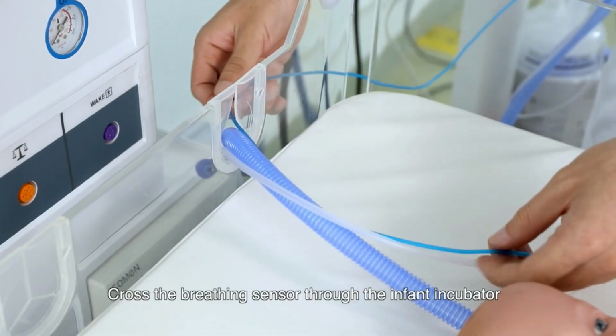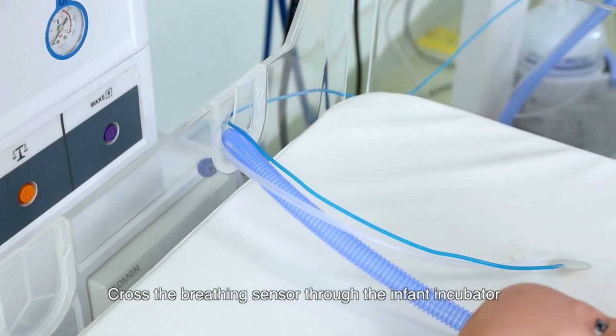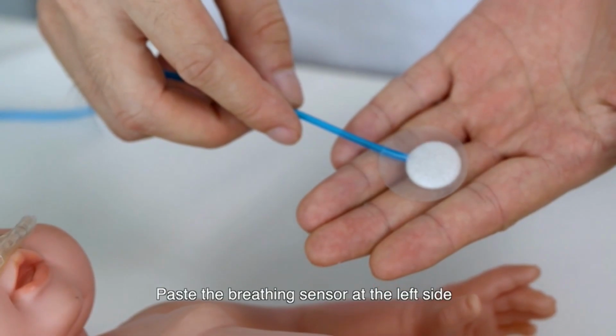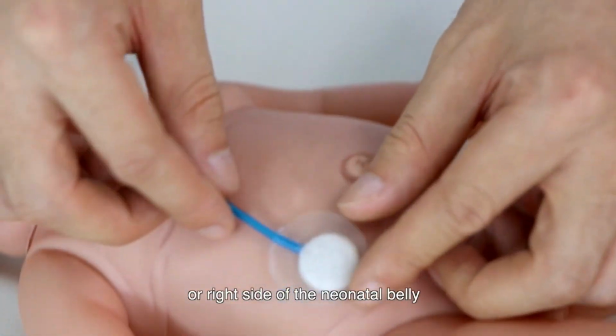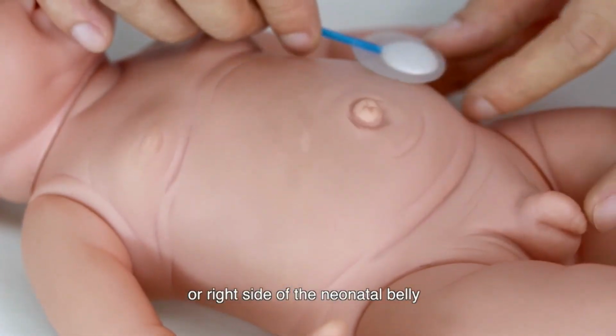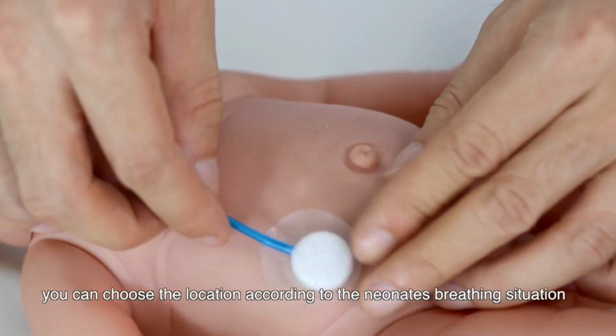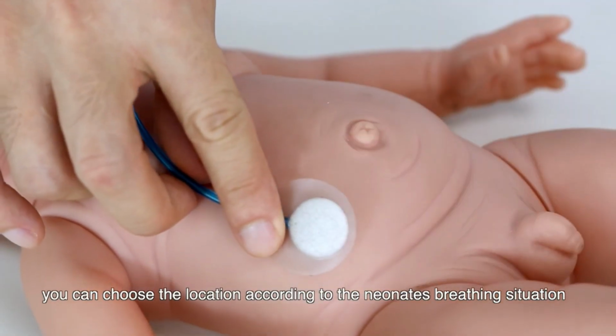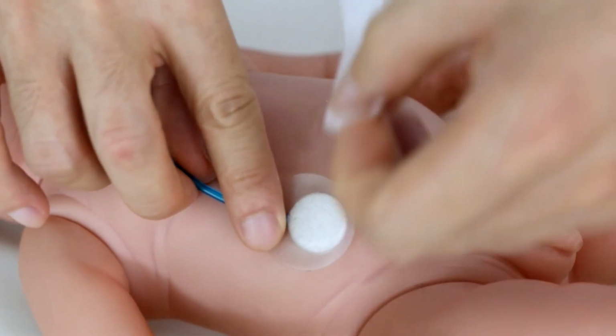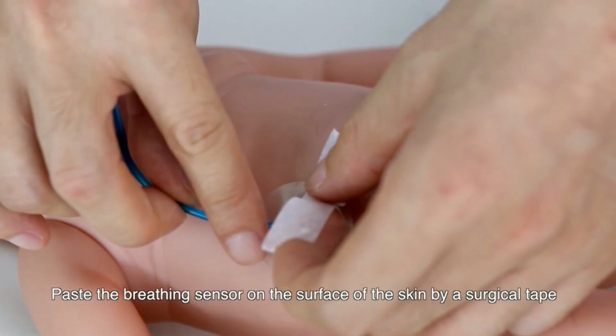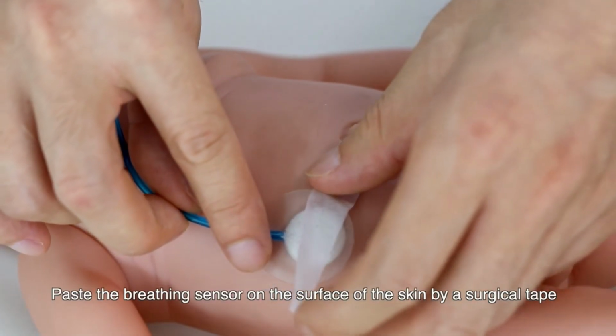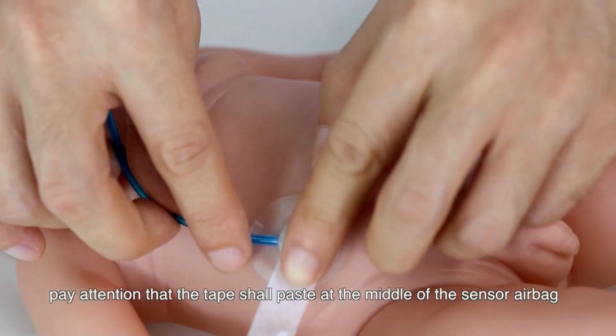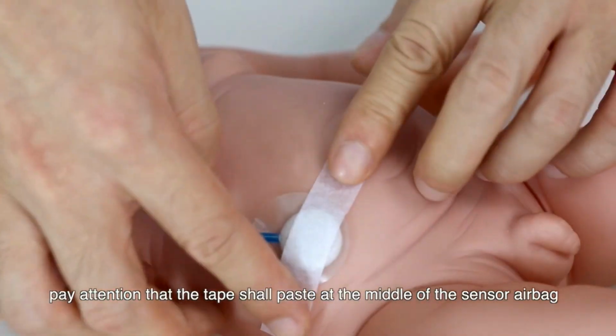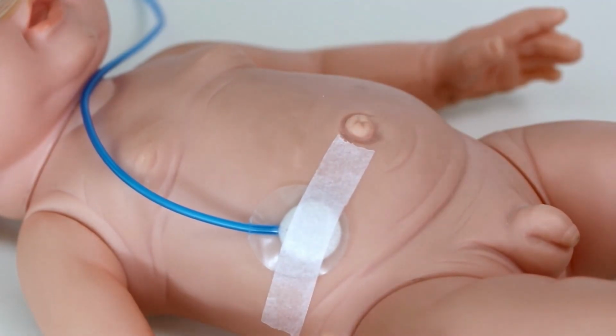Cross the breathing sensor through the infant incubator. Place the breathing sensor at the left side or right side of the neonatal belly. You can choose the location according to the neonate's breathing situation. Paste the breathing sensor on the surface of the skin by a surgical tape. Pay attention that the tape shall be pasted at the middle of the sensor airbag.